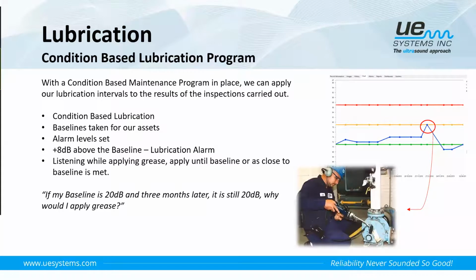One question you could also state is that if I set my baseline and the baseline is 20 decibels, for example, and I have a PM that tells me to go back out and lubricate that bearing, and I go back there and the reading is still 20 decibels and it's smooth and uniform, do I need to apply grease? Does that bearing require grease because it is still the same level of sound as it was 3 months ago, for example? We're doing condition-based lubrication, not just because we think it needs it, we're doing it because the bearing tells us it needs it. So this is a good way of using ultrasound for condition-based lubrication.